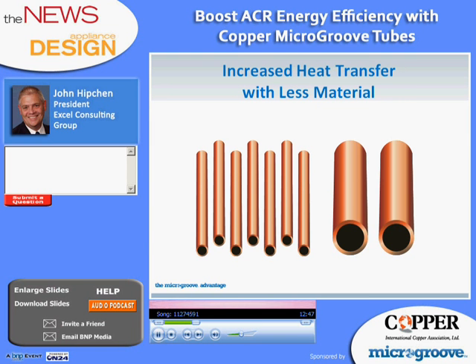And as we continue to reduce tube diameters, we continue to gain surface area in relation to the amount of refrigerant that we have in the tube. And we can continue to reduce tube wall thicknesses while still meeting the same pressure criteria as the larger tubes. So looking at this from a different angle, we can handle higher pressures in smaller diameter tubes with the same tube wall thicknesses. The bottom line to all of this is that we can do a lot more with considerably less material when we use smaller diameter tubes.